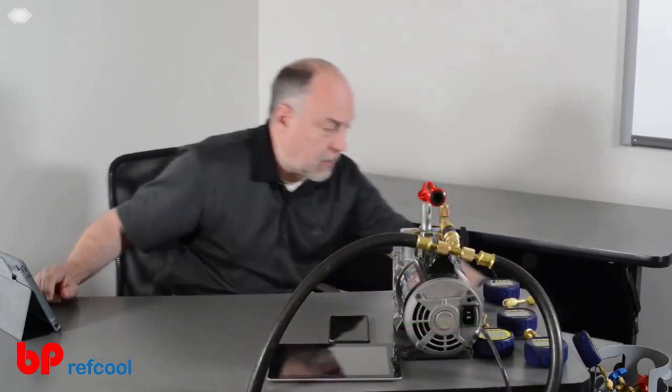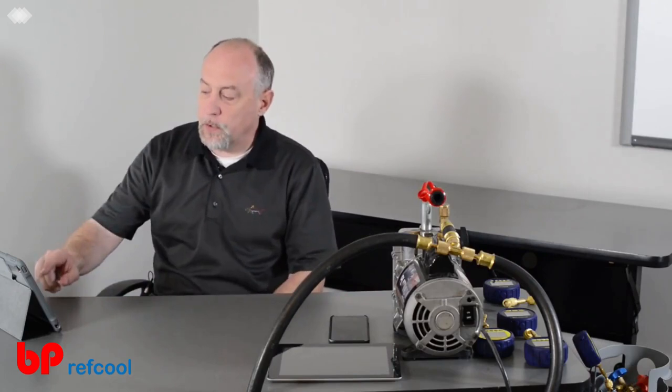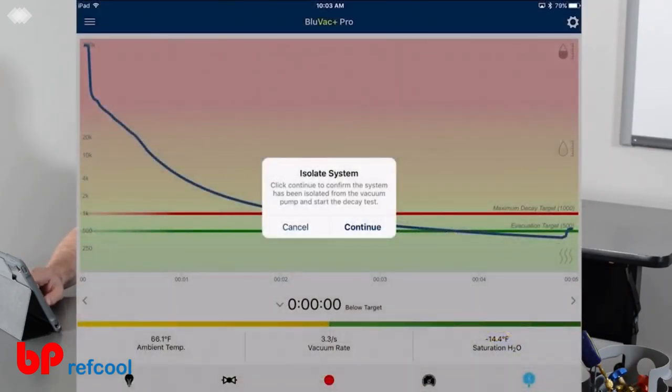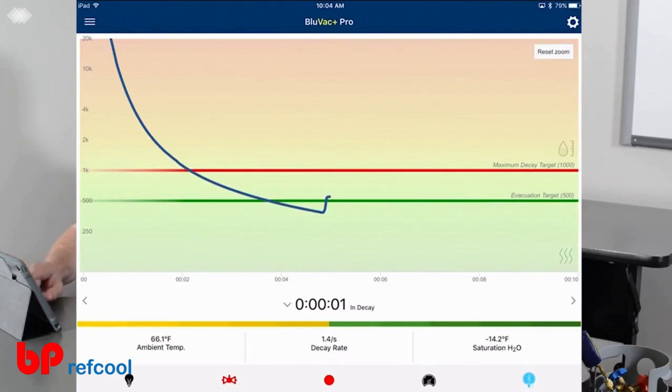Now it's held below the target for a period of one minute. I'm going to go ahead and close off my core tools. When I close off my core tools, you're always going to see a little bit of a decay in the vacuum.